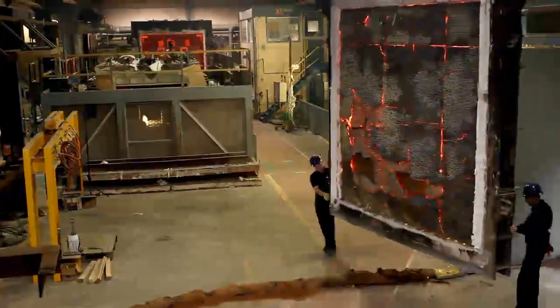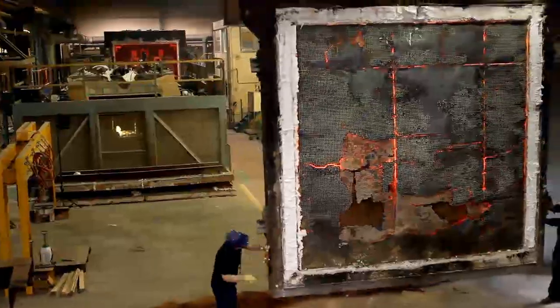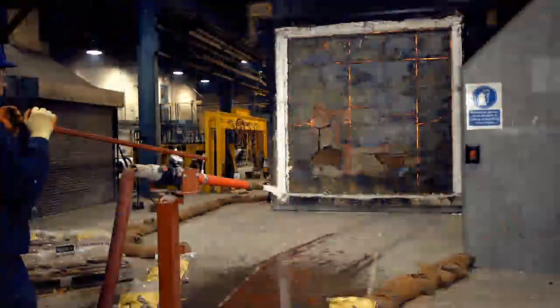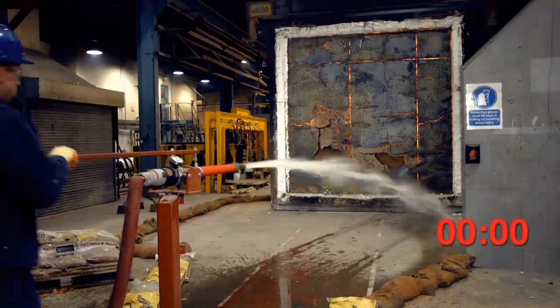The final part of this test is to prove whether Durasteel can withstand a hose stream sprayed evenly over the surface for five minutes at a pressure of 310 kilopascals or 3.1 bar. This is to meet the integrity requirements of UL ASTM E119-12.